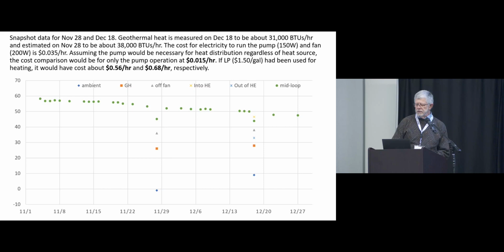The yellow X on the 18th of December is the temperature going into the heat exchangers, and the blue X is the temperature coming out. The orange box is the temperature in the greenhouse, and the triangle—I can't quite tell what color that is—is coming off the fan. So off the fan, the temperature drops just going through the greenhouse because it's passing over the glazing and cooling off. But from going into the heat exchangers and coming out, there's about 13 degrees difference.